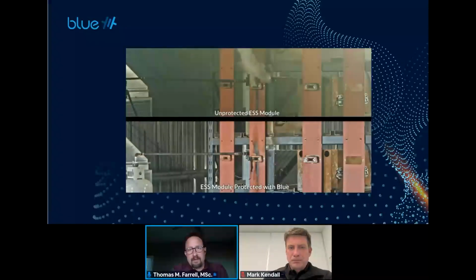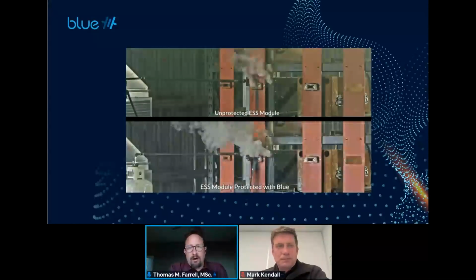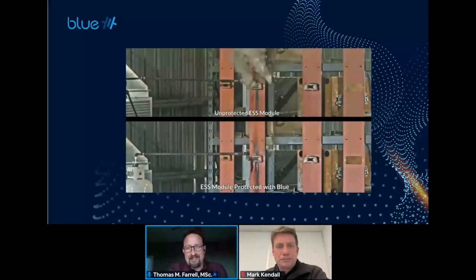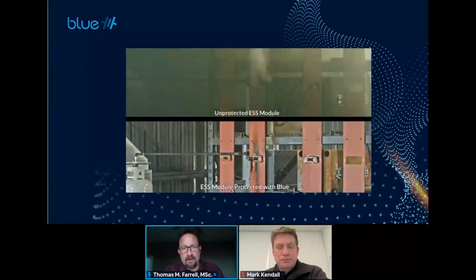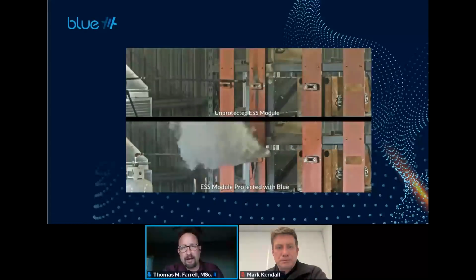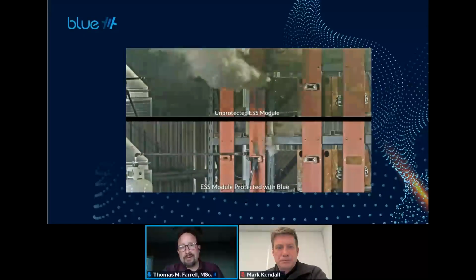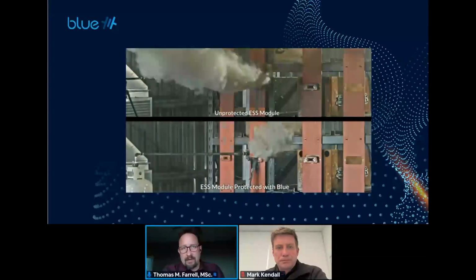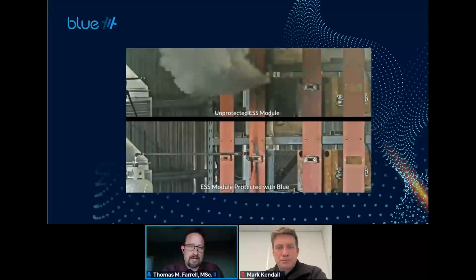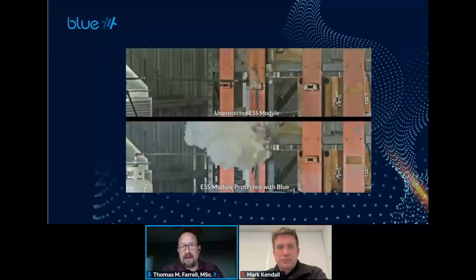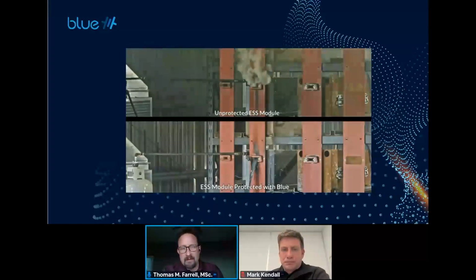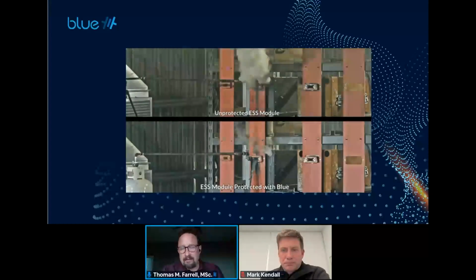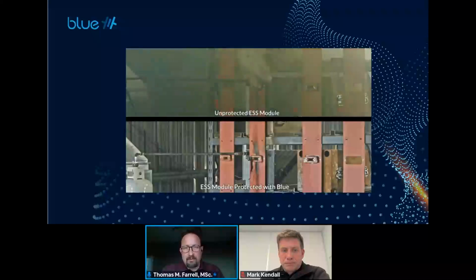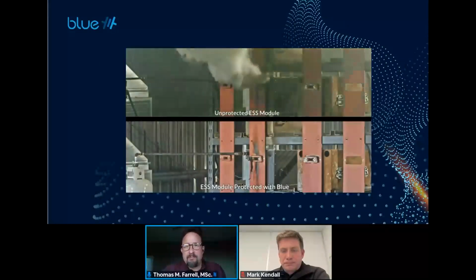One more note about the quality of those gases: the gases coming off the lower video with blue are extremely saturated. We've recently done additional testing with another client using a much larger battery, NMC chemistry as well, trying to ignite these particular gases. We know those tend to burn, and if not flaring, they generate a high level of hydrogen and methane. We were unable to ignite that flammable mixture because it was so saturated with vapors from blue.